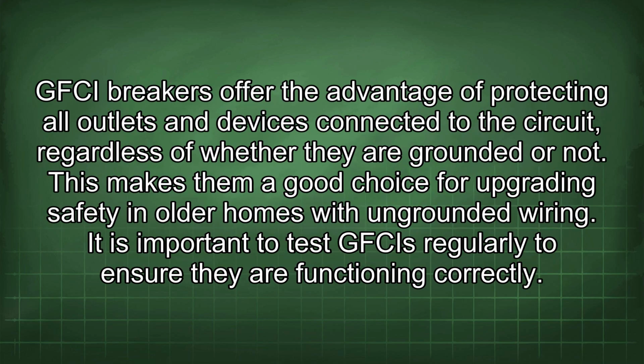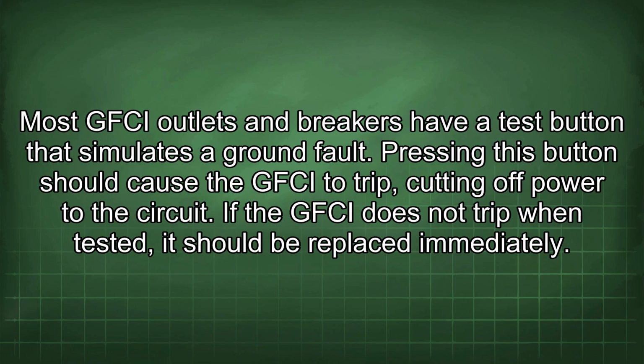GFCI breakers offer the advantage of protecting all outlets and devices connected to the circuit, regardless of whether they are grounded or not. This makes them a good choice for upgrading safety in older homes with ungrounded wiring. It is important to test GFCIs regularly to ensure they are functioning correctly. Most GFCI outlets and breakers have a test button that simulates a ground fault. Pressing this button should cause the GFCI to trip, cutting off power to the circuit.